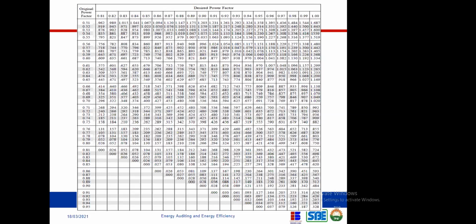If you look at the top, you see desired power factor. When you look at the next row, you see different values of power factor. So you have to look at the value of power factor that you desire. Then on the first column on the left, you will see original power factor. So if you have an inductive load in your house and it's affecting your power factor, for example a power factor of 0.7, and you want to correct it to 100%, you trace that 0.7 across up to the point where you have 100%. So you see 1.02 there. That becomes your table factor to improve that 0.7 to 100.